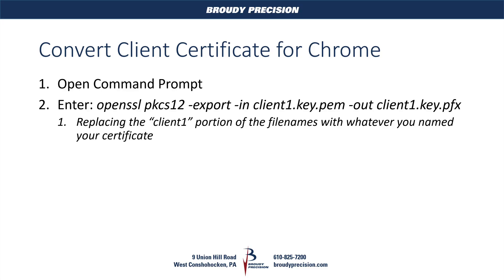We've exported our certificates from Niagara and now we have to get them ready to be put into Chrome. The issue is that Chrome doesn't like a PEM file with a key in it, so we have to do a file conversion using OpenSSL from the command prompt. OpenSSL is an open-source tool that is the de facto standard for working with certificates — it can convert certificates from one type to another. In our case, we're going to convert from a PEM file to a PFX. The only difference for you would be changing the filename to match yours, and importantly we're using the version with the private key in it.